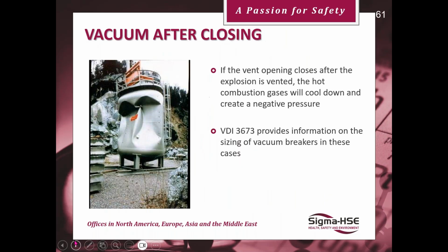I've seen them full of bird's nests and powder around them. As I said, after closing, this is what happens if the vent closes too soon. You get a vacuum and your vessel is destroyed. So be careful when you're using the doors.